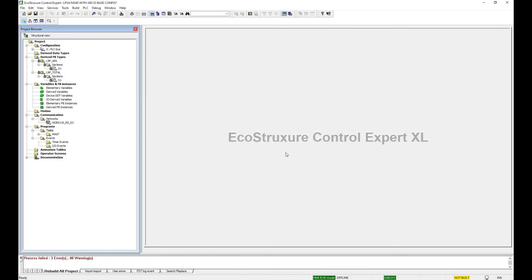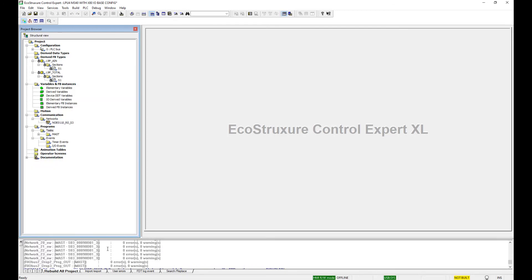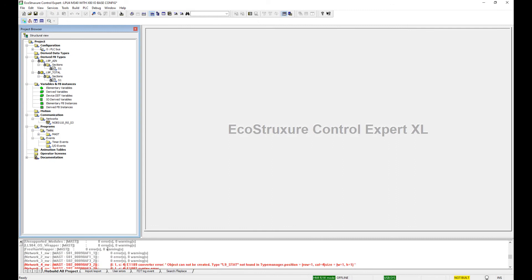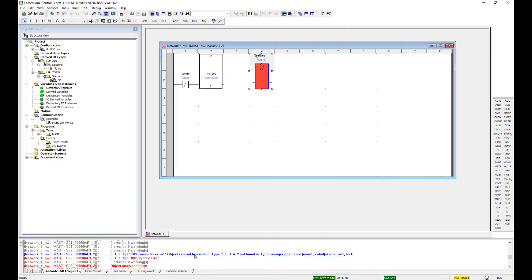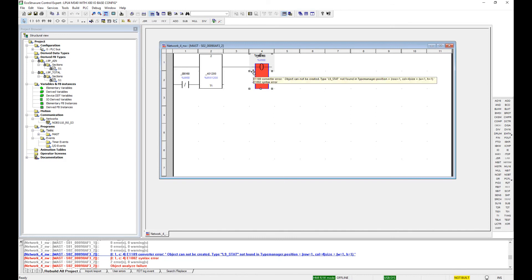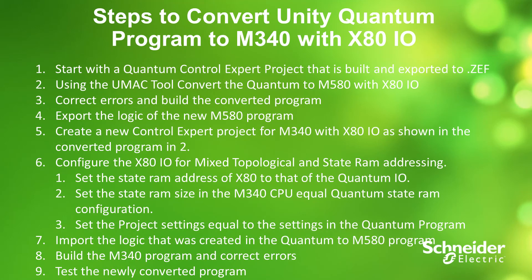When we get done here we have three errors that will need to be addressed. If I go to those errors, it says object cannot be created. It is an L9 stat block that's not supported in the M340. So then you would just need to manually go in and create whatever logic you need to take care of that stat block, or the stat block might just be deleted completely. And that's how you convert a Quantum project to an M340 project using the UMAC tool.